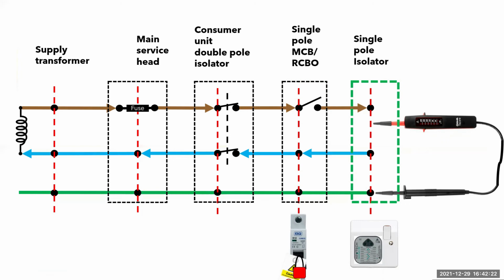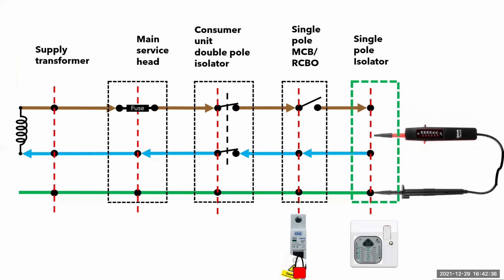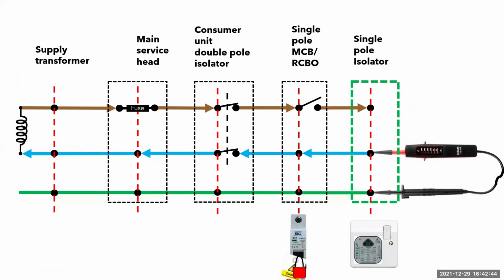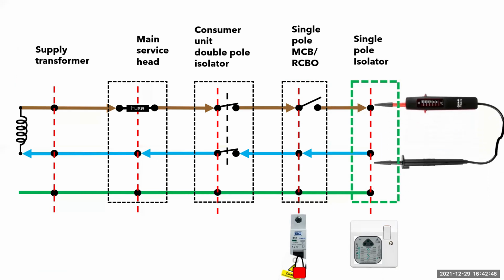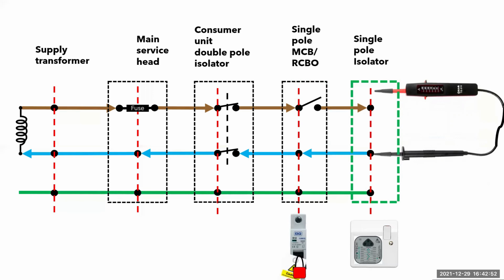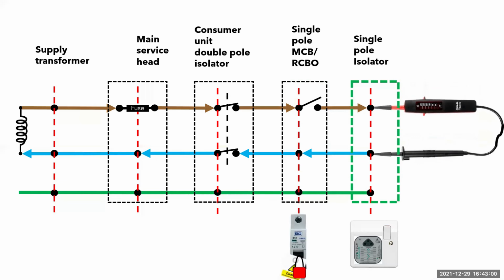It's a good idea to put the test probe onto the earthing conductor first so that you don't have the other end potentially live. So put the probe first on earth, then test to the line conductor. Remove from the line conductor first, and then, still with the probe on the earth, come to the neutral, remove it from both. As the neutral is safer than the line conductor, put one of your test leads on the neutral first, and then bring the test probe to line to test between neutral and line conductors.